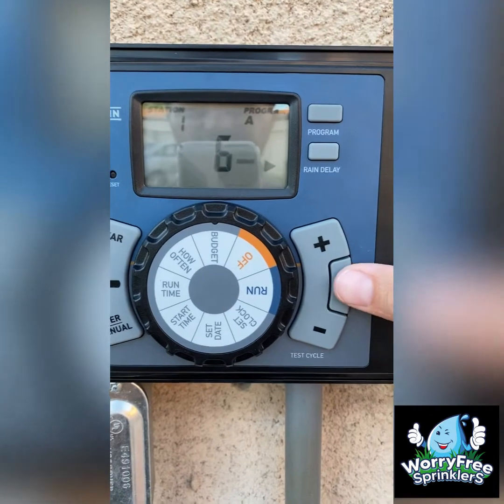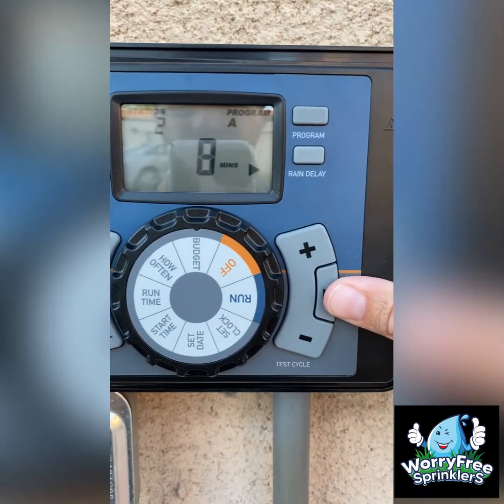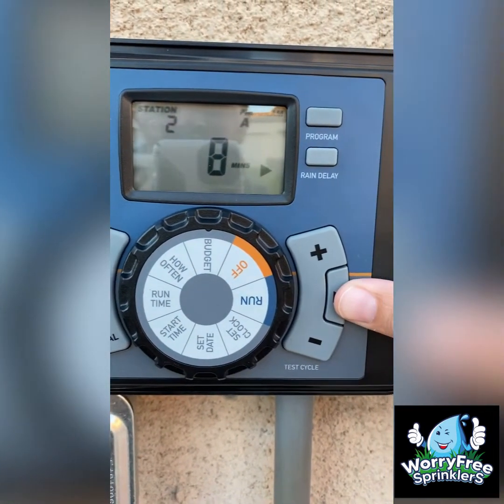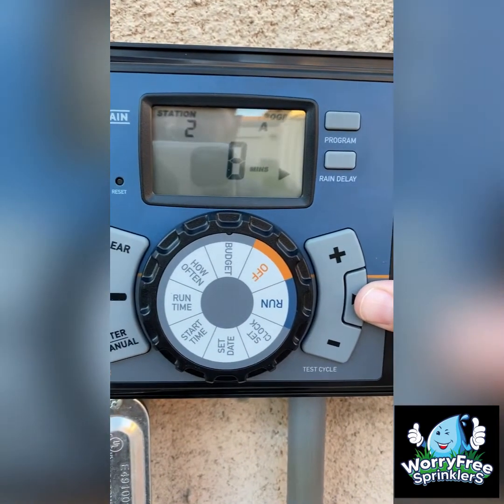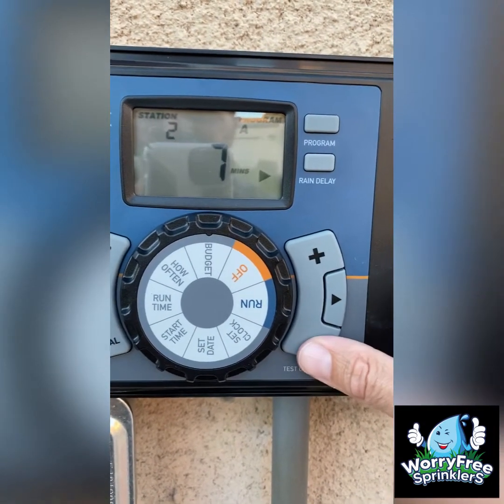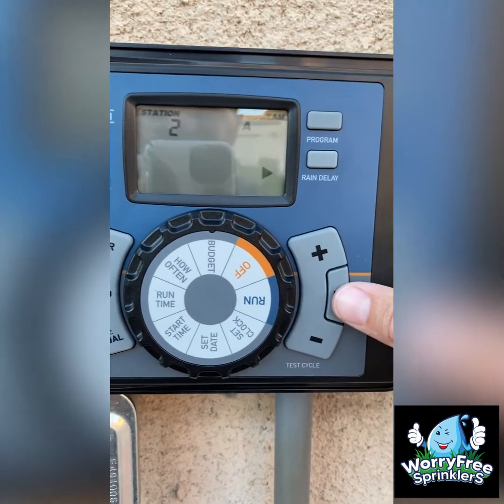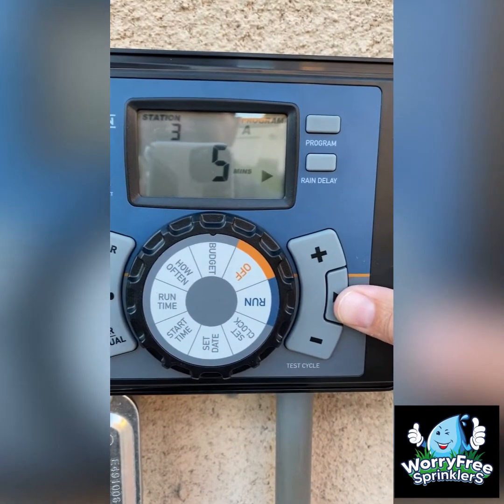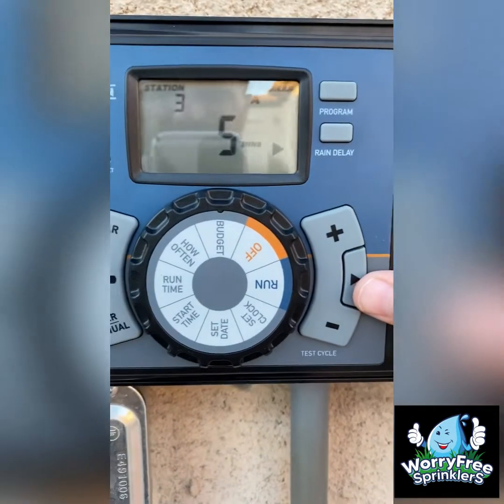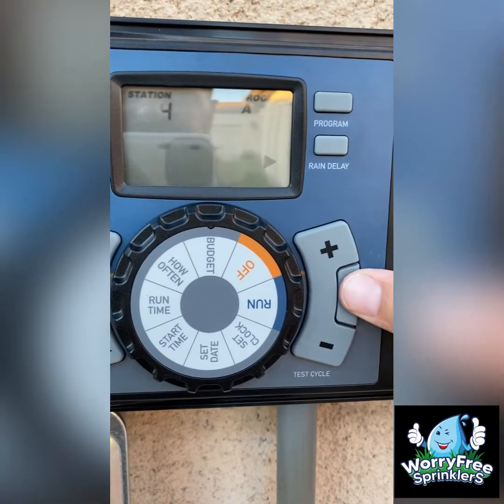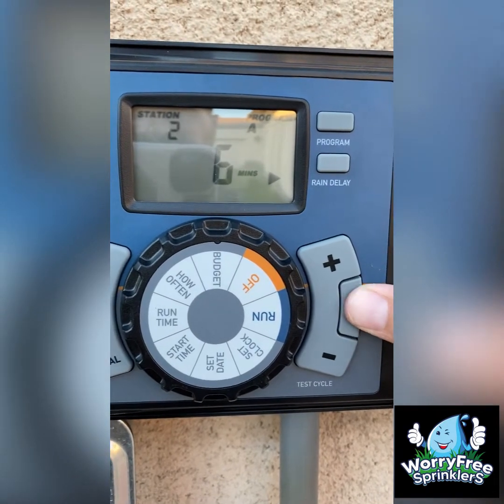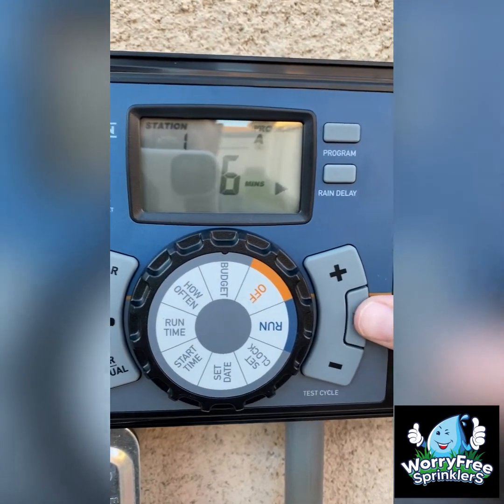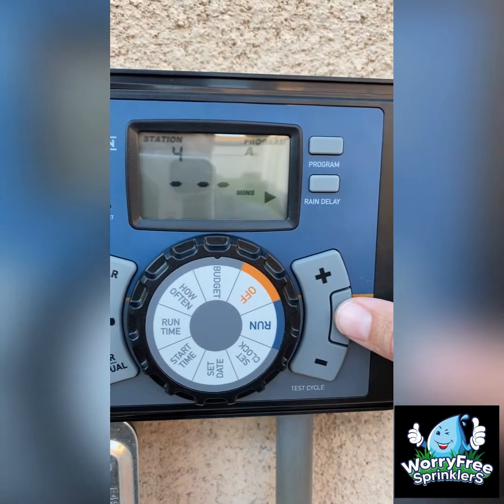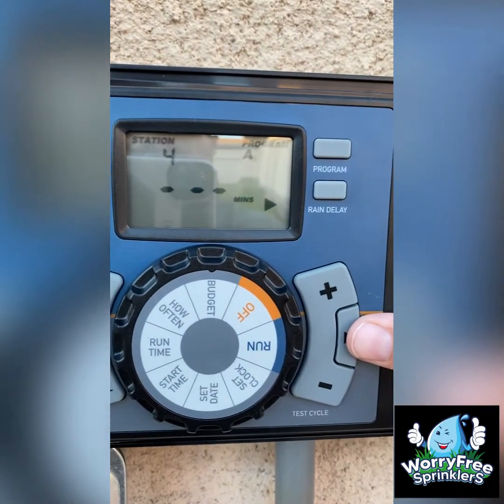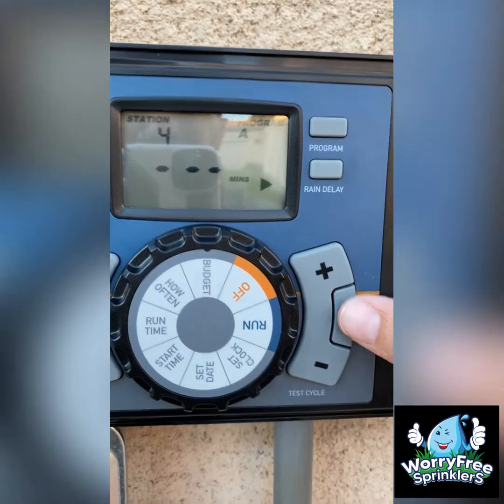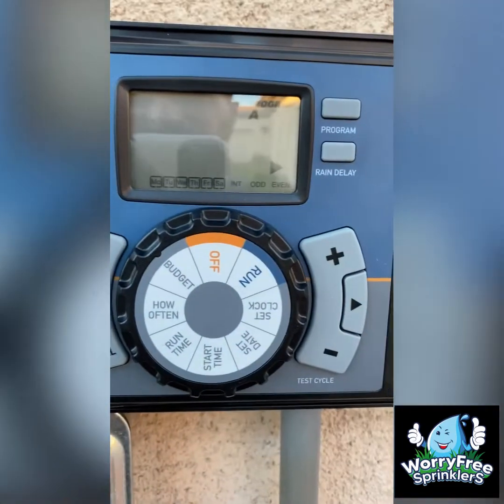Station 1 is my drip line. Now my station 2, or zone 2 or whatever you want to call it, station 2 is my sprinkler system. So we're going to go ahead and lower that to 6 minutes as well. Station 3 is also my sprinkler system in the backyard, so 6 minutes, and we don't have a station 4, so it's just simply a 3-valve system, and so that's the only ones you want to program. If there is a 4th valve and you don't have one hooked up, just put that to 0.